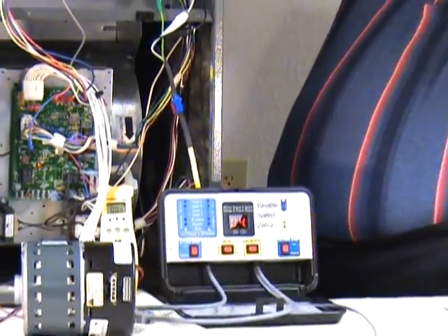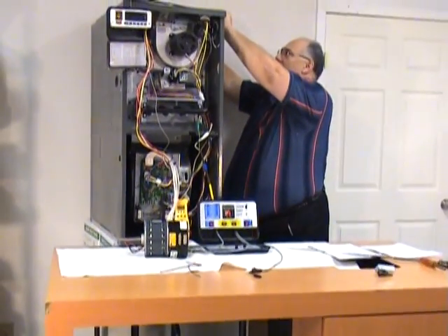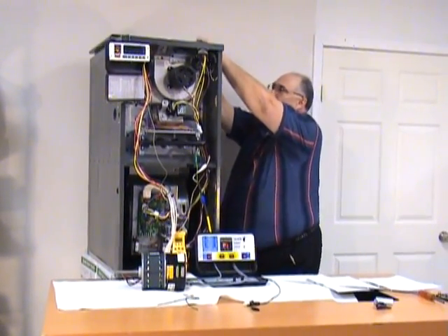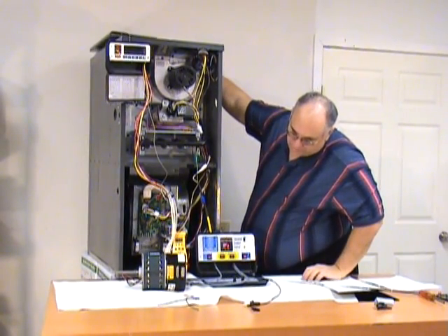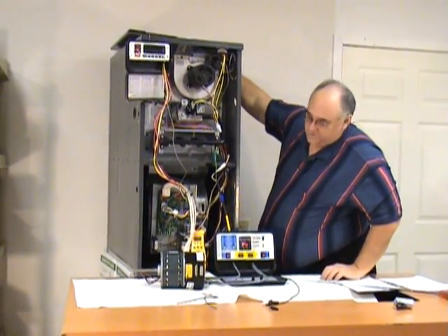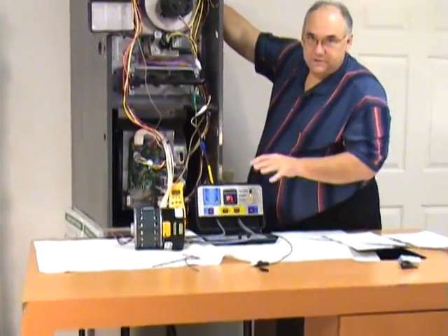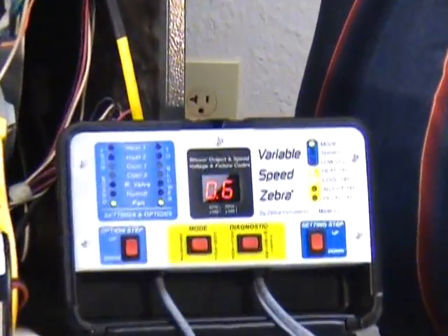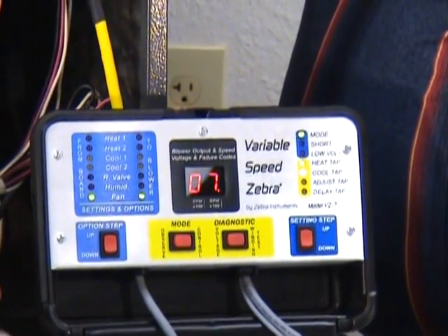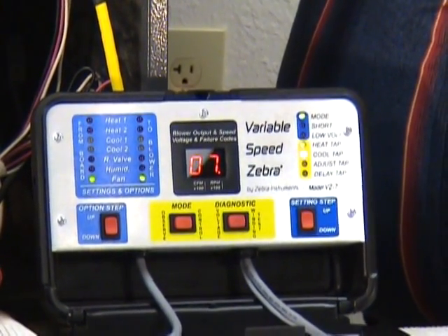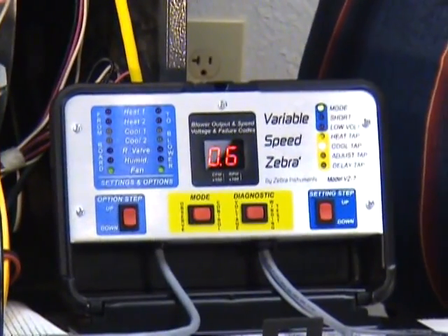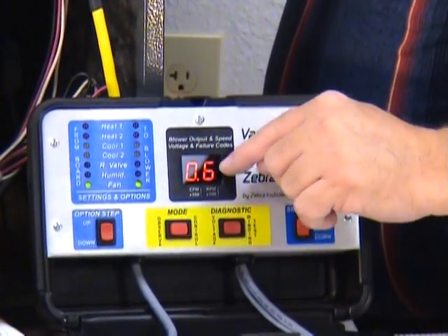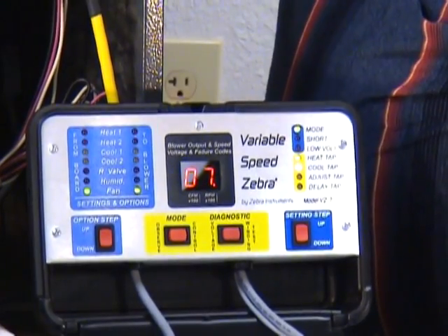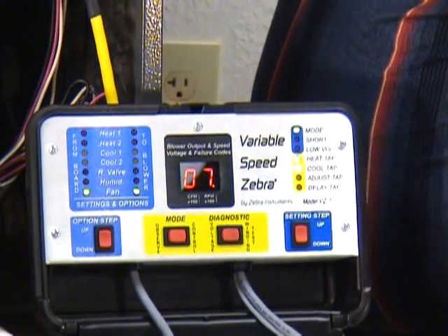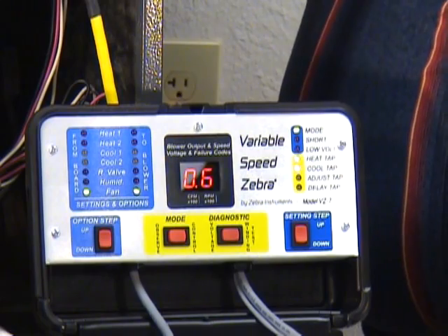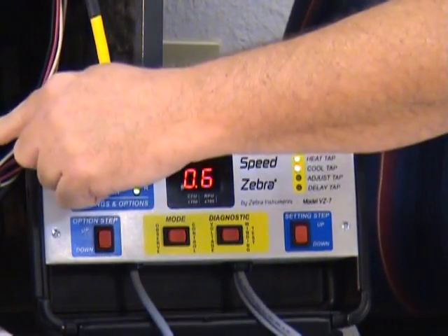What's neat, and I like to demonstrate, is if you put something on top of your furnace to block some of that air, thereby increasing your static pressure, that motor will speed up dramatically. Remember, it takes a few seconds for this display to stabilize. That motor will speed up dramatically to try to maintain the same CFM. So it's speeded up, it's still pumping 600 CFM, and it's increased its speed to 700 RPM instead of 400.